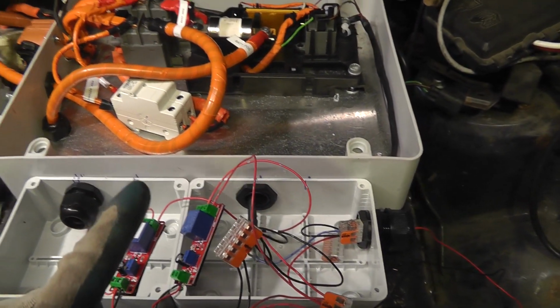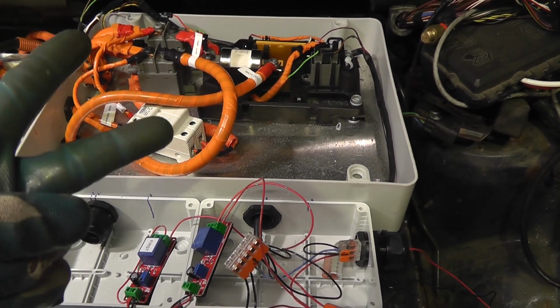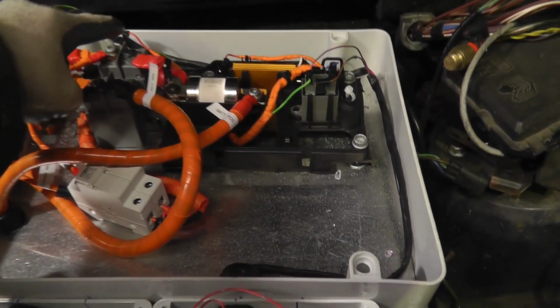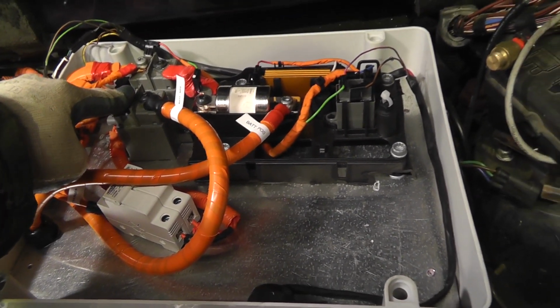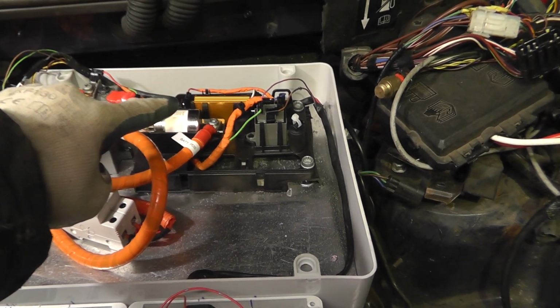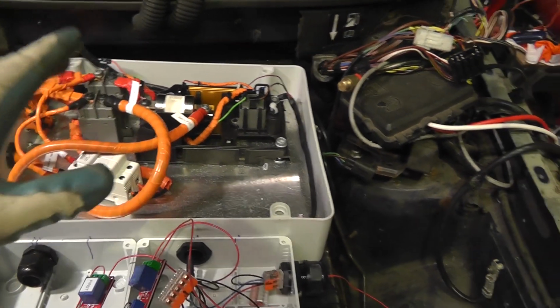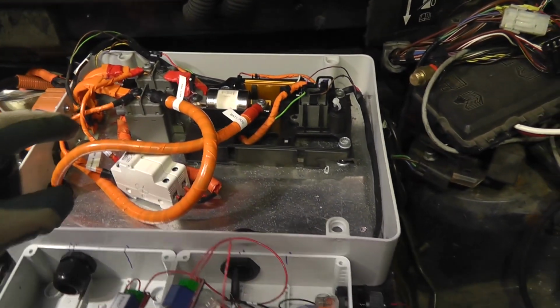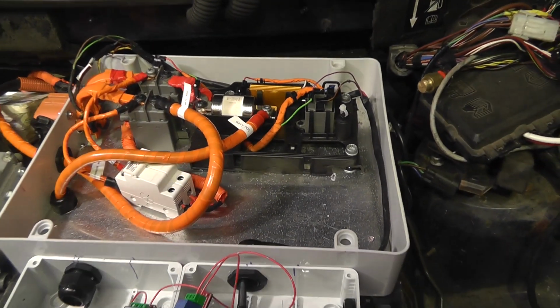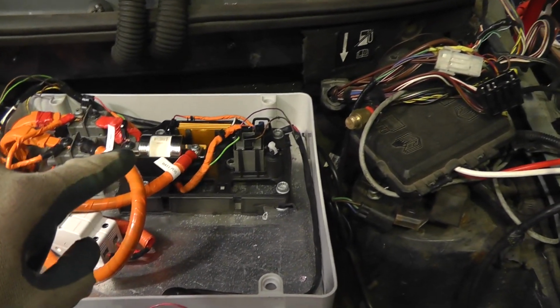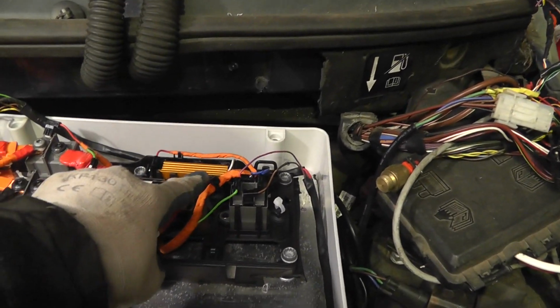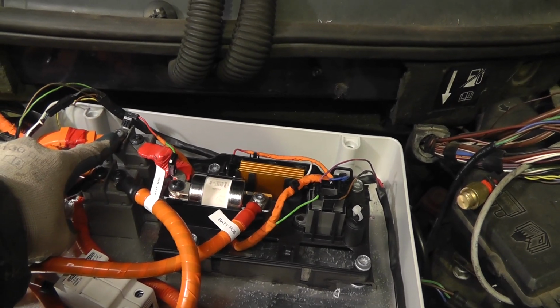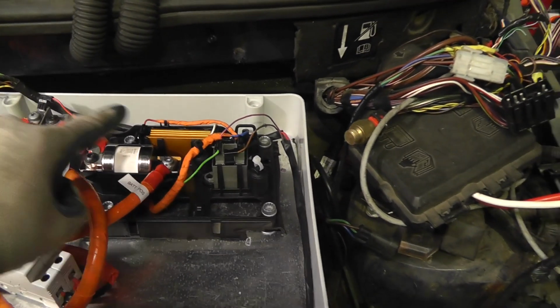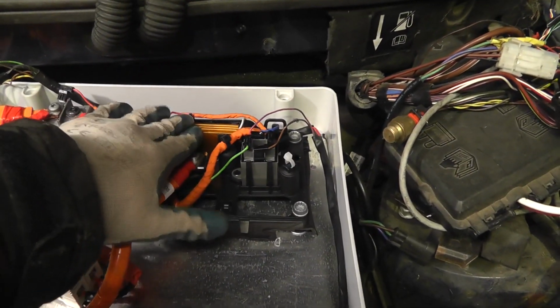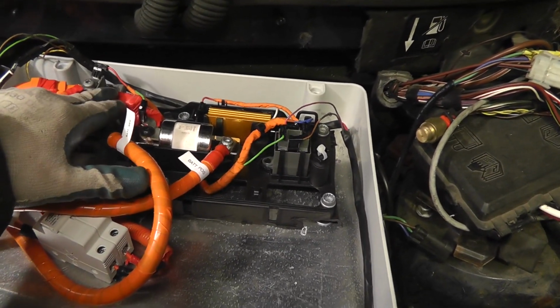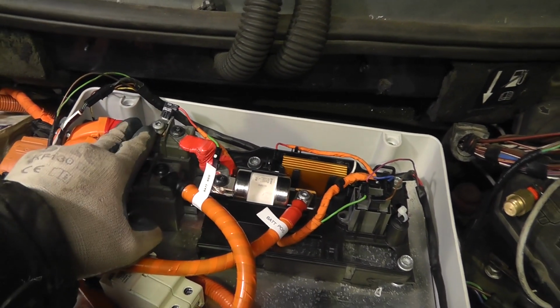I cannot afford to have the positive and negative go through the main contactor at the same time as going through the resistor. If that was to happen, if it was to lose the correct timing, it would damage these contactors - they would end up being fused. So what you have to do is trigger your 300 volts so that it goes through a resistor first, and after a second or two of the voltage building up gradually through the resistor, you then trigger the main contactor, which allows the voltage to go straight across the contactor.